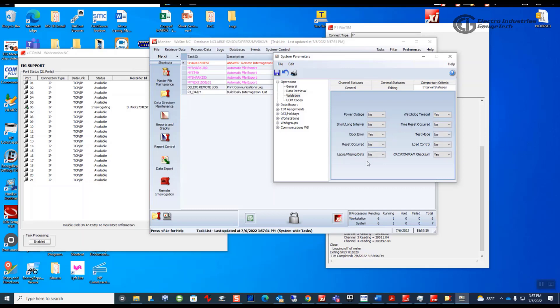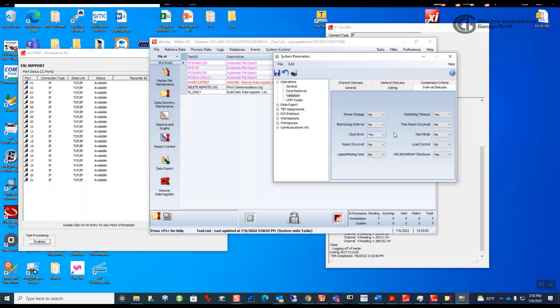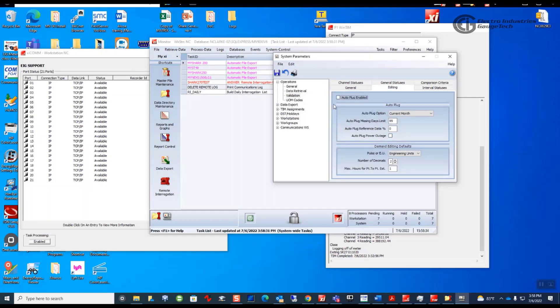Test mode is not turned on to flag, so that's not why it failed — I can rule that out. CRC or RAM error checks are serious issues. Clock errors are also checked — if the TIM identifies a clock problem in the meter, it would fail because it's set to 'yes.' Anything set to 'yes' will be rejected if it comes up as an issue in the event logging. Short and long intervals are set to 'no,' and power outages is turned off, so none of these caused the rejection.